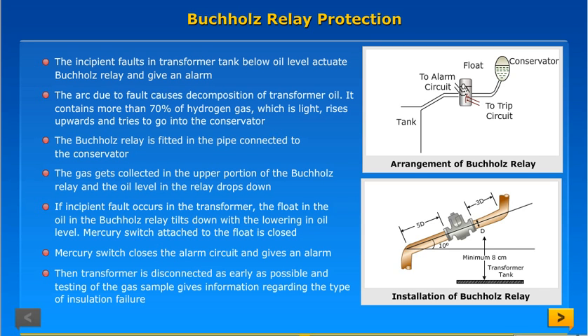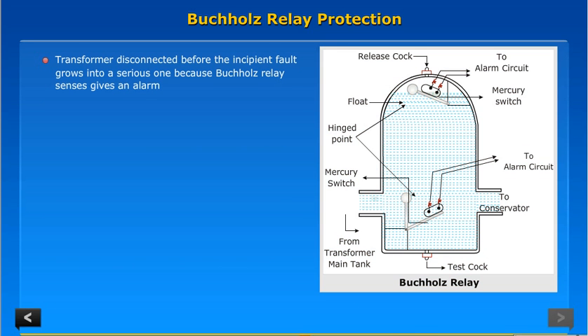The transformer is disconnected as early as possible and testing of the gas sample gives information regarding the type of insulation failure. The transformer is disconnected before the incipient fault grows into a serious one, because the Buchholz relay sensor gives an alarm.